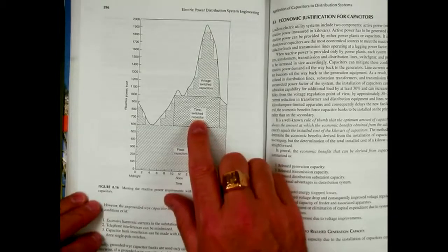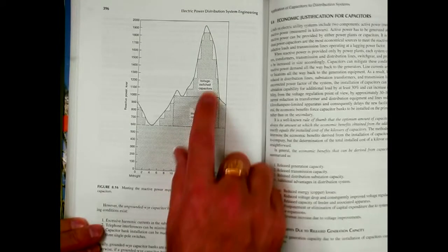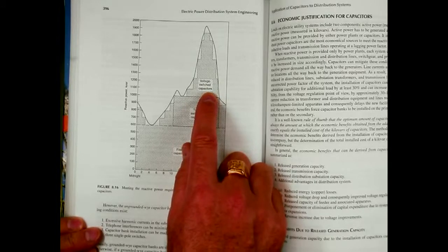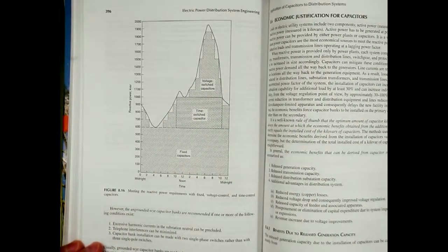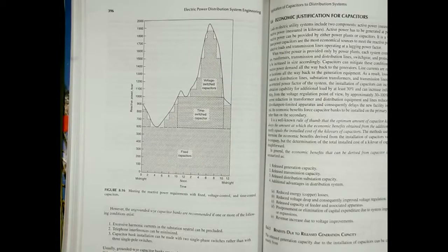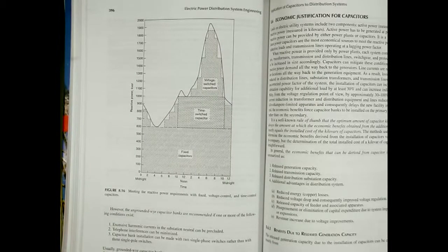And so basically here is time switch control, that's your T, and this is voltage switch, right? And you have done that, and you see that when you have too much current, which is a lagging power factor, what's happening? The voltage drops. And when it drops below 95% or certain, you know, so here is sensing.